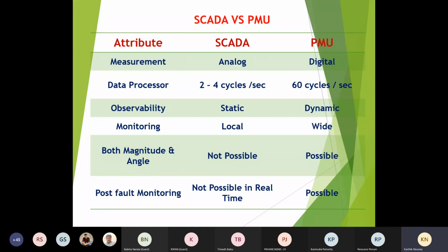Then the attributes, and what are the parameters that PMUs will use to replace the SCADA units. From the measurement point of view, SCADA will give you analog, but PMU it is a digitalized quantity. In data processing, SCADA is 2 to 4 cycles per second in olden days, but PMU is 60 cycles per second. From the observability point of view, SCADA takes only the static, not the dynamic position. The meaning of dynamic is in live operating conditions, this phasor measurement unit can give you the voltages and angles exactly, whereas SCADA monitors only wherever the RTUs are considered. SCADA will take the data from remote terminal units and it will monitor only locally.